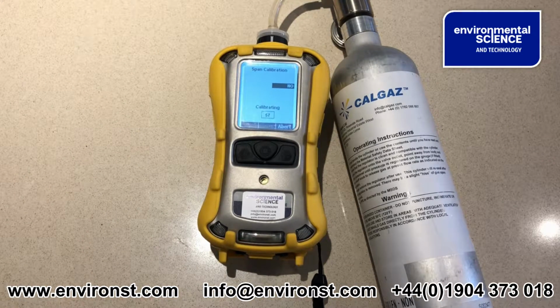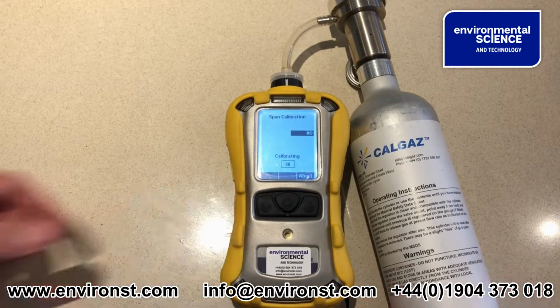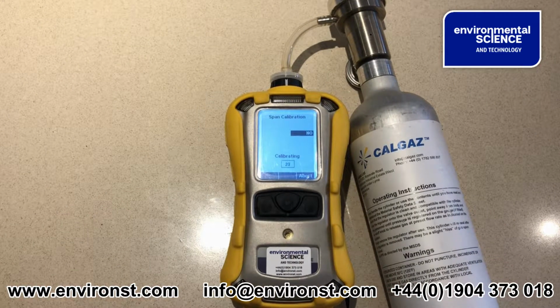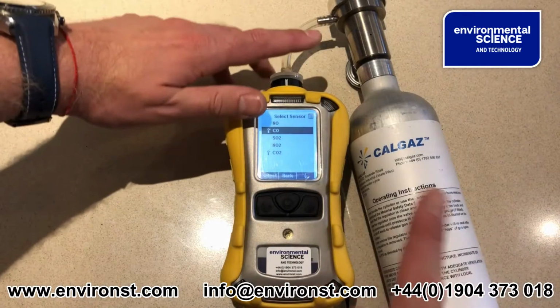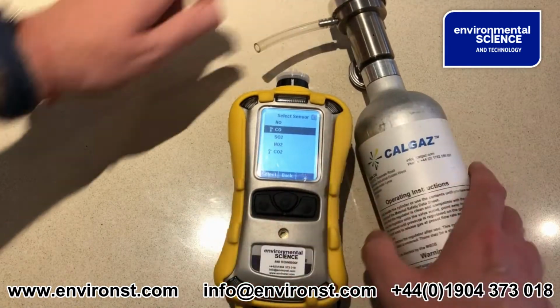So you can see here it automatically detects the gas and is now calibrating to 50 parts per million. So this is now coming to the end of the calibration. You'll see it flick through and tell you what the actual reading is. So it's now saying 50 ppm passed. And you've got a slight waver there, but that's very normal when you're looking at these sort of concentrations. So now we're done, we remove the gas.